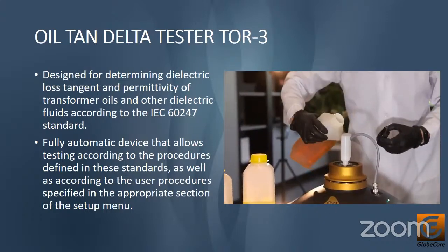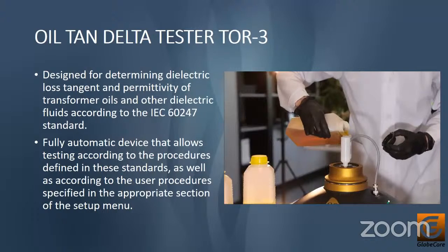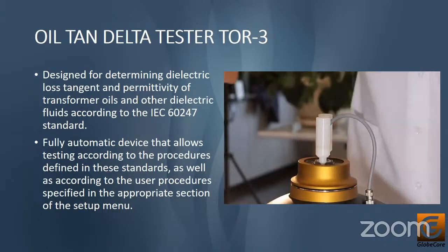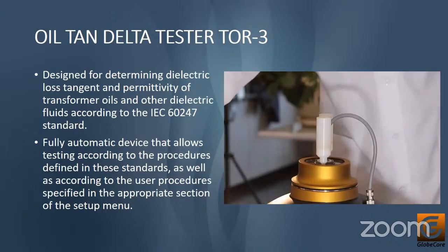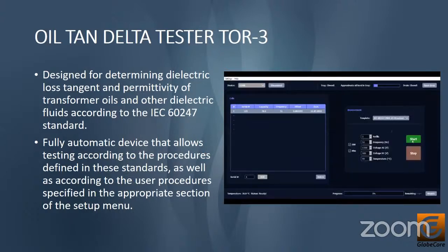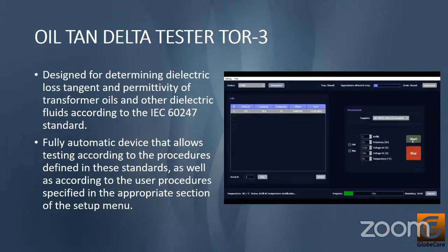This device is controlled by a computer which commands certain actions. Measurements are made in automatic mode with the results output to this computer. After connecting the device to the mains, a command can be sent to the unit to begin measurement, which is usually performed with oil at 90 degrees Celsius. The heating takes most of the measuring cycle time.